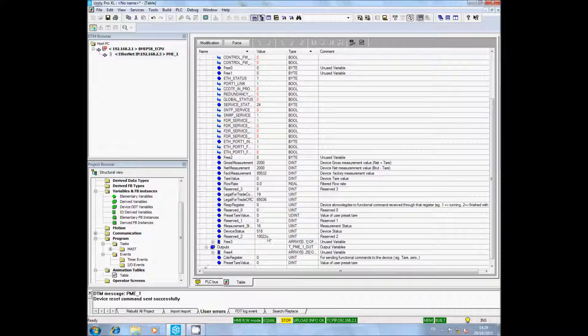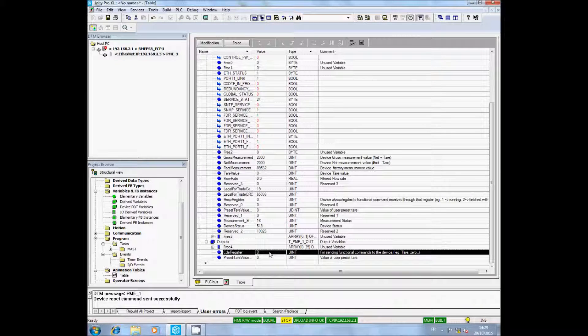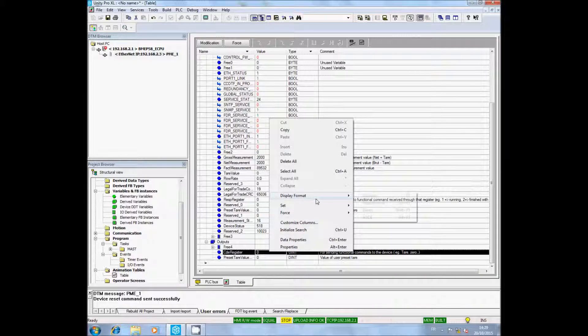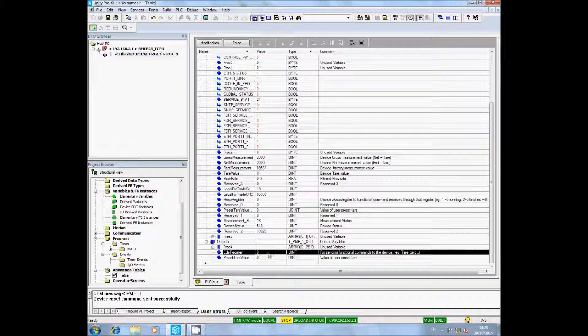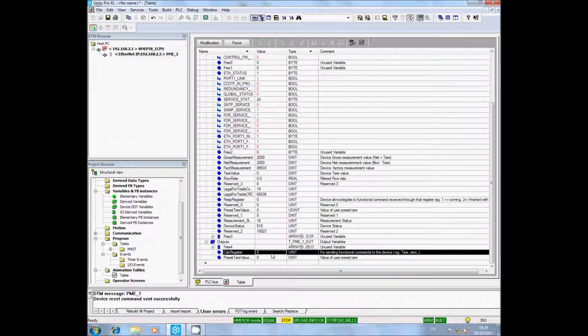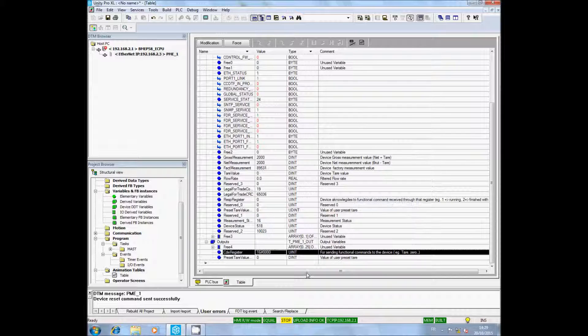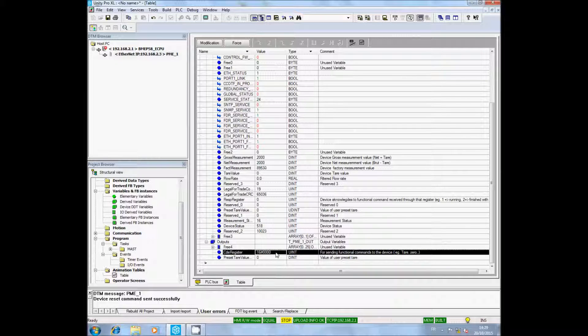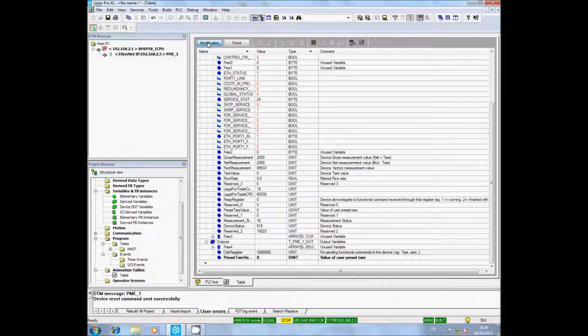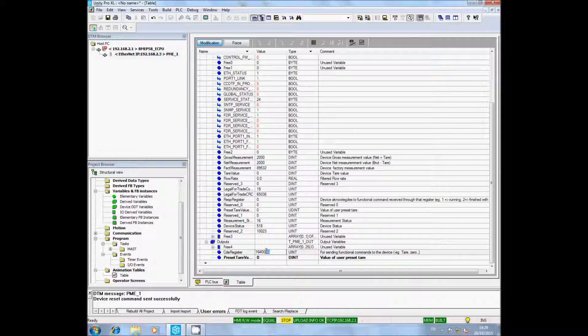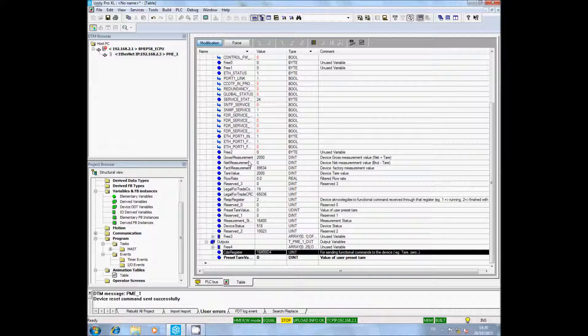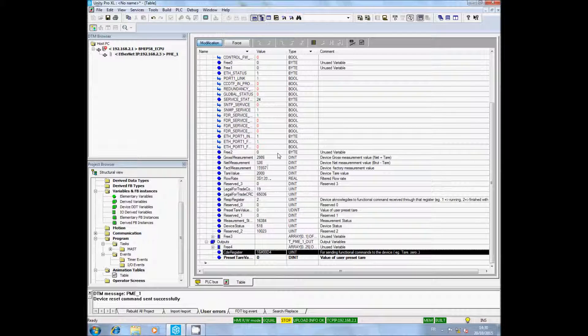If you unroll the output menu, you will find the command register and the response register. Here I will put the command register in hexadecimal to match with the user manual. If I send the command 00D4 for the tare, you can see the net weight is set to zero. You are now ready to use the PMESWT.